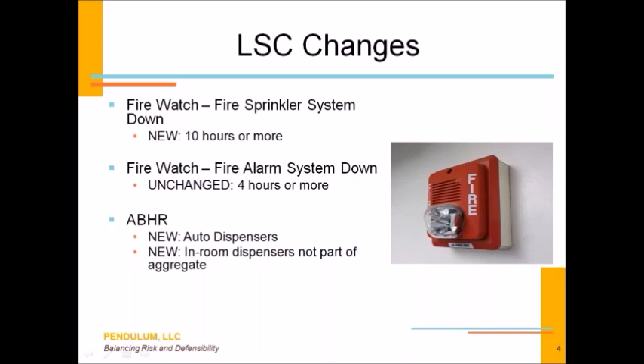When it comes to other elements of operation, specifically in reference to infection control, I walk into healthcare facilities all the time, and I see those alcohol-based hand rub dispensers everywhere. Well, there is some allowance of a specific amount of those devices within individual smoke compartments, and here's what you need to know. Within a smoke compartment, within the means of egress, so that means the common areas that lead to an exit, generally we're talking about your hallways, you're limited to 10 gallons of that alcohol-based solution.